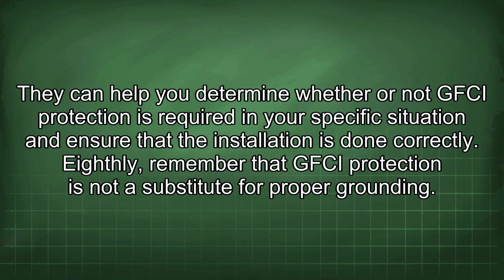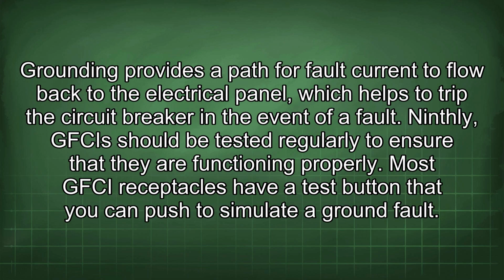installation is done correctly. Eighthly, remember that GFCI protection is not a substitute for proper grounding. Grounding provides a path for fault current to flow back to the electrical panel, which helps to trip the circuit breaker in the event of a fault.